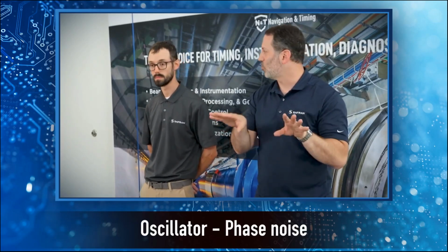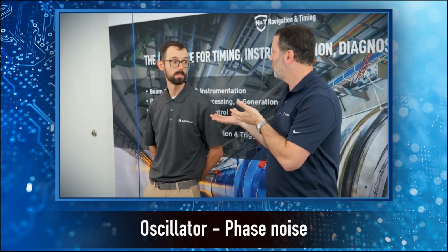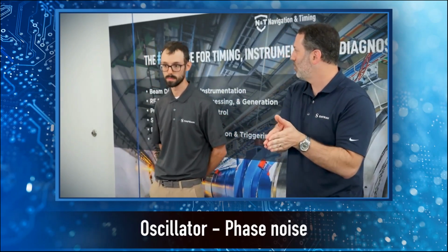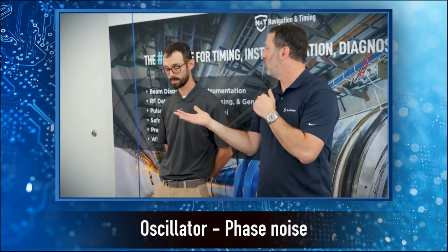The better signal allows you to better distinguish between those as you're doing overlaps across that application. And so there are unique effects as we go across the oscillator, and then there are combination effects, like the low phase noise rubidium, where that's actually combining the benefits of the holdover from the rubidium and temperature effects with the low phase noise outputs for those specific applications.